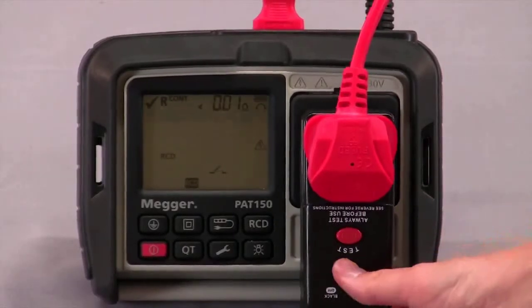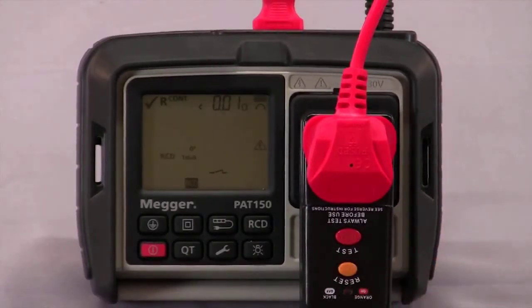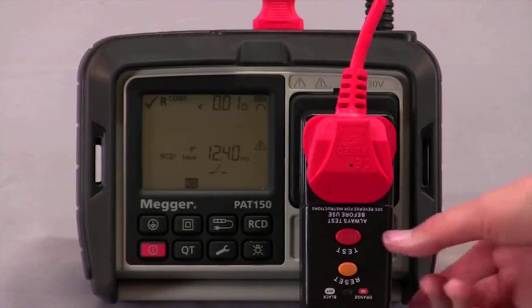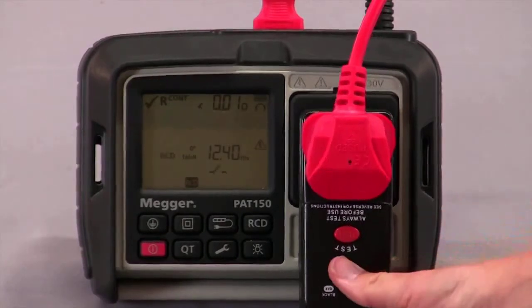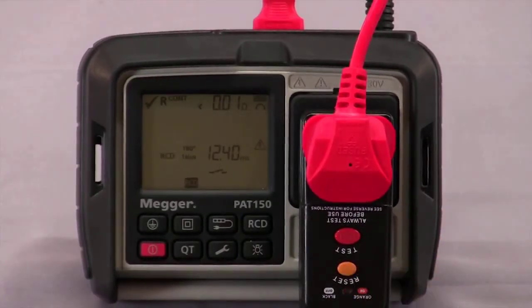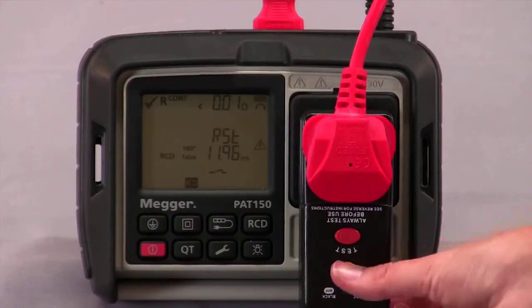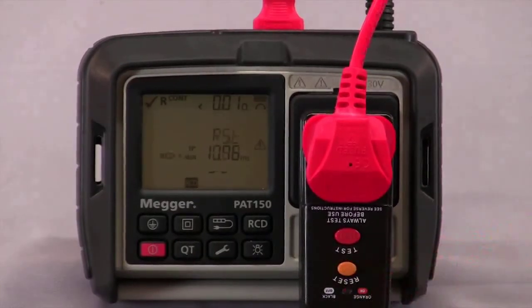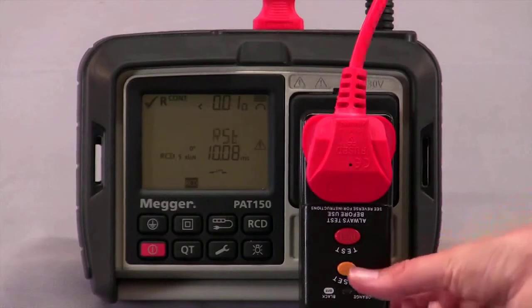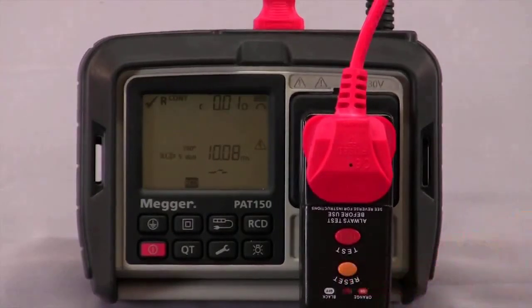Reset the RCD again. It's displaying my trip time for 1 times. Reset it again, and this will do my 180 degree. Reset it again, this will move on to my 5 times, and reset it again for my 180 degrees. It will then proceed to tell me if it's passed or failed with the tick or cross.